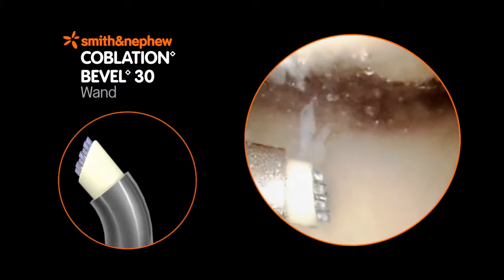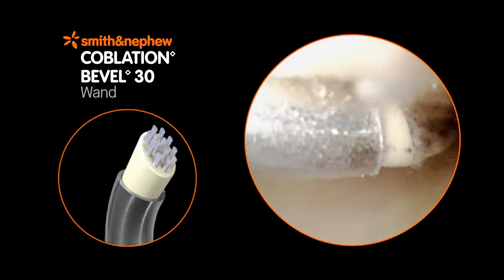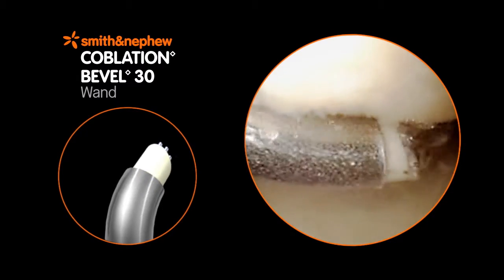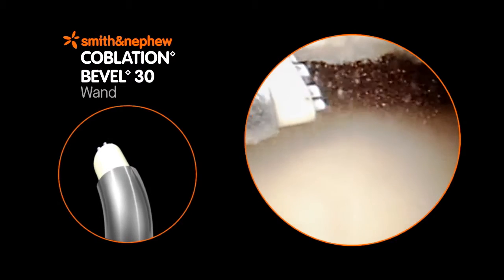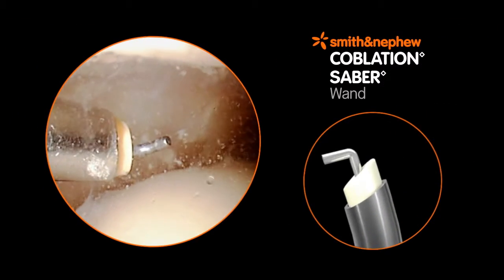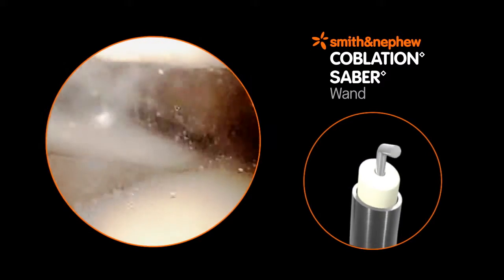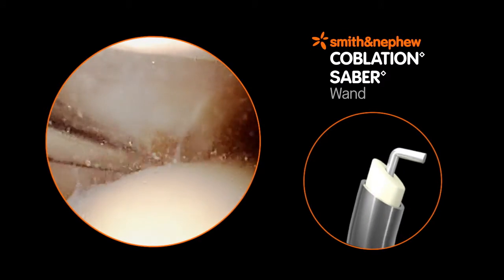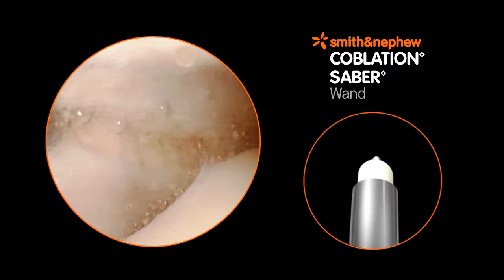The bevel Coblation wands have versatile cutting angles in slimline designs for ease of insertion and access. The bevels are available in three shaft angles — 30, 45, and 60 degrees — for a wide variety of surgical applications. The Saber Coblation Wand uses a single hooked electrode to cut and coagulate all types of soft tissue, and is especially useful for procedures such as lateral release, in which a focused cut is necessary.